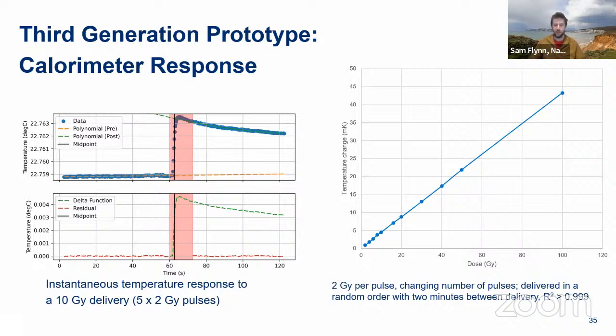This is 2 gray per pulse, which is very, very FLASH. You look at the pulses here, they are microseconds long, so this is mega gray per second instantaneous dose rate. This is the best case scenario where the calorimeter works really well, but an ionization chamber will struggle. And we saw that on the day when we did this, that the reference monitor chamber lost all its sensitivity because it wasn't able to do any relative measurements.